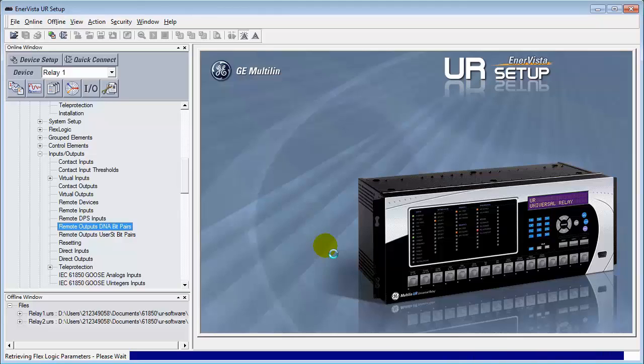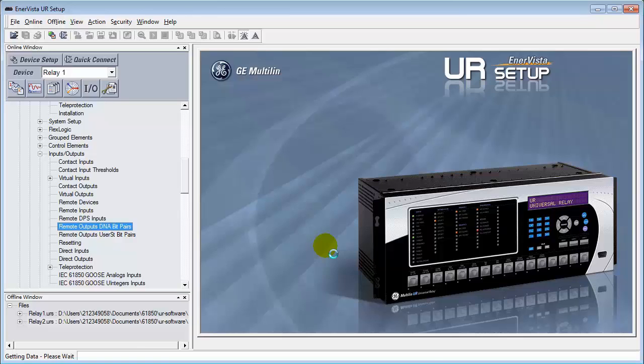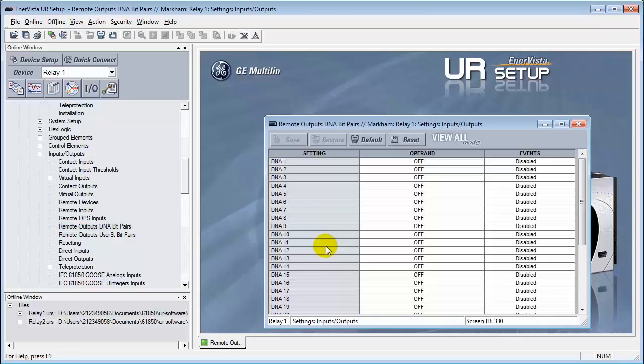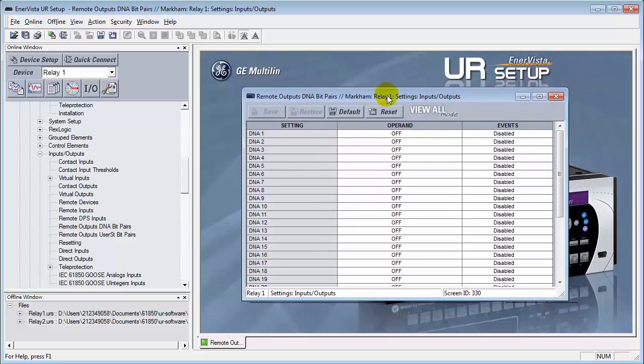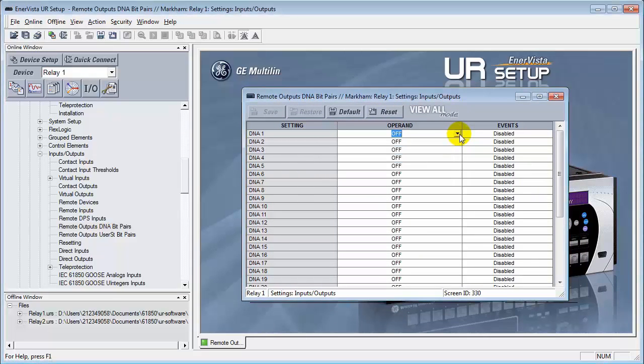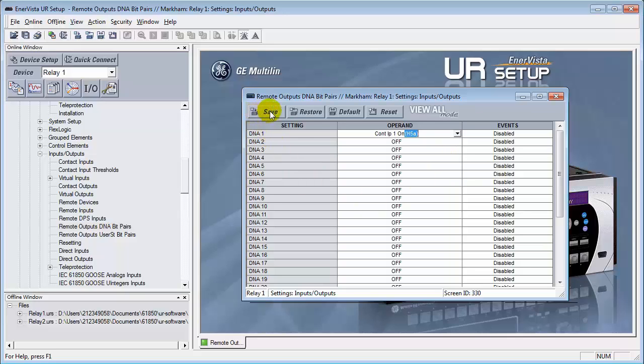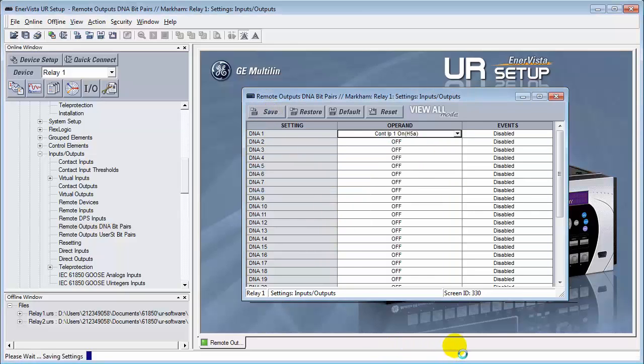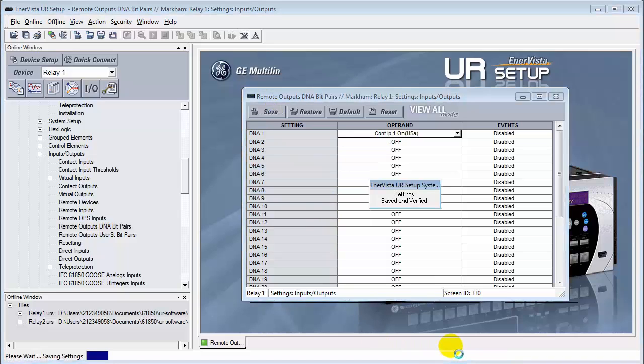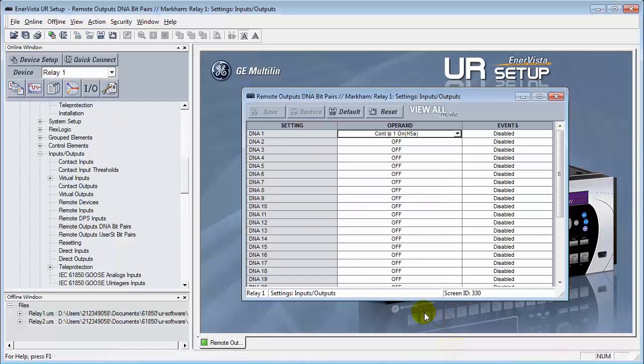This can be a breaker status. It can be a contact switch status. This can be a protection element. Because all we're doing is sending here is a digital signal. So in our case, let's go with contact input number one. So we can type it in. Contact input one on. So that means every time the switch closes, we're going to be sending the goose message out. Or if it opens or if it closes. Every time the state changes, we're going to be updating the network immediately. So we click on save. This concludes the publisher part of the fixed goose.